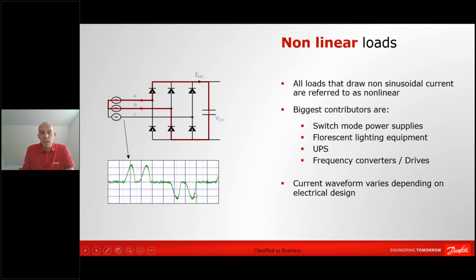So if you take a VSD and you map the current in front of the VSD, you will see a pulse shape similar to the green curve that you have underneath here. You will see the same if you took a switch mode power supply. Of course, if it's a single phase, it looks a bit different, but for 3 phase devices, it looks the way that you have down here. Now, every component that has this kind of behavior is referred to as nonlinear. And there is, as said, a lot of these non-linear loads on your supply or on your network, and they all draw non-sinusoidal current waveforms. And that's actually what we need to look at now. What is the flip side of these non-sinusoidal current waveforms?